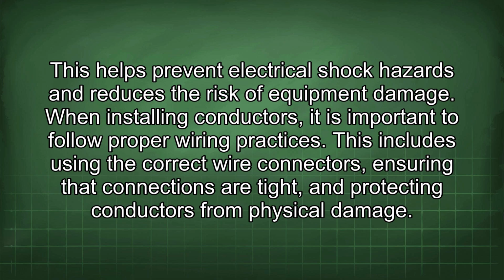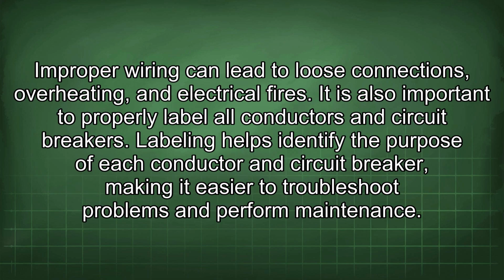When installing conductors, it is important to follow proper wiring practices. This includes using the correct wire connectors, ensuring that connections are tight, and protecting conductors from physical damage. Improper wiring can lead to loose connections, overheating, and electrical fires. It is also important to properly label all conductors and circuit breakers. Labeling helps identify the purpose of each conductor and circuit breaker, making it easier to troubleshoot problems and perform maintenance.